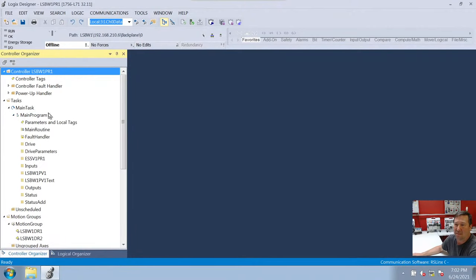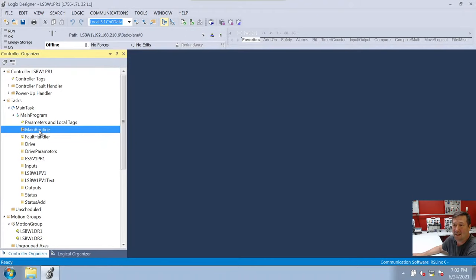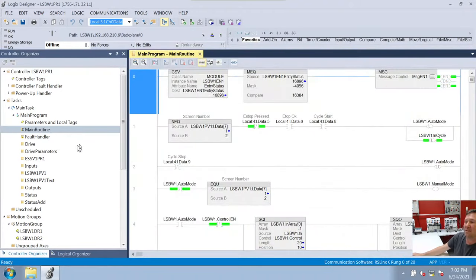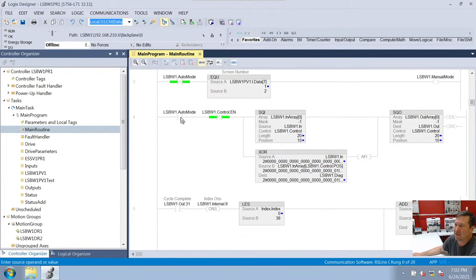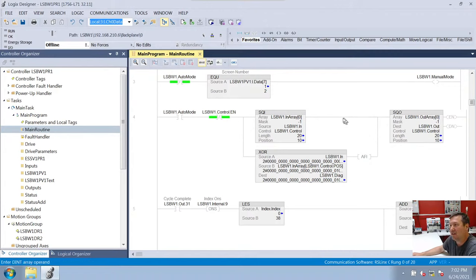We're going to go into the main program. By now I figured out how to make subroutines. In my previous program, I had everything dumped into Ladder 2 — that was an RSLogix 500 program. Now I've figured out how to break things up. When I opened the main routine, I cringed right away, mainly because of this sequencer logic right here. A lot of you have asked me to go over how it works, and really I have not gone over it because I don't think this is a good way to sequence machines.